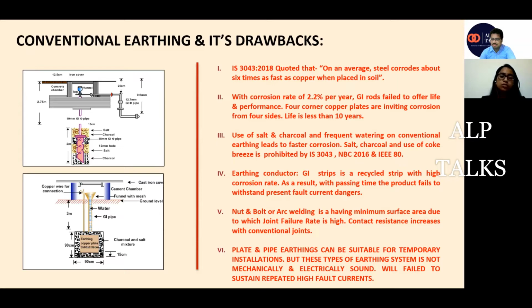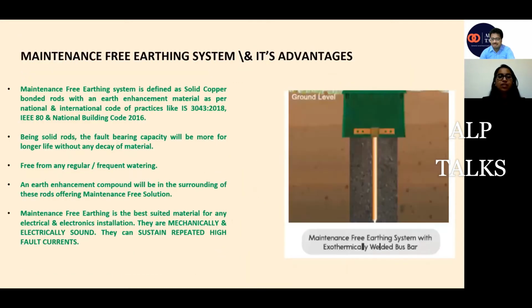And also, for GI installations, the National Building Code itself says that GI should be used for temporary installations. For permanent installations, we should go for copper bonded steel or copper material. GI shall not be used for permanent installations when it comes to a lightning protection system. So it is also a recommendation from the National Building Code. It should be copper only for lightning; copper bonded steel we can also use, where we have a copper coating over steel. So there are much better materials as compared to GI.